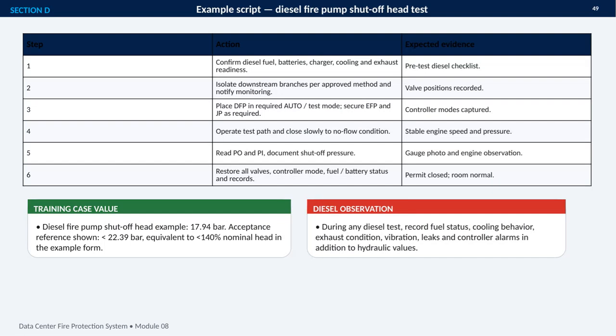This slide provides a practical example script for a diesel fire pump shutoff head test. The sequence begins with readiness, confirming fuel, batteries, charger, cooling, and exhaust conditions before operating the pump. Next, downstream branches are isolated using the approved method. Monitoring is notified and valve positions are recorded.